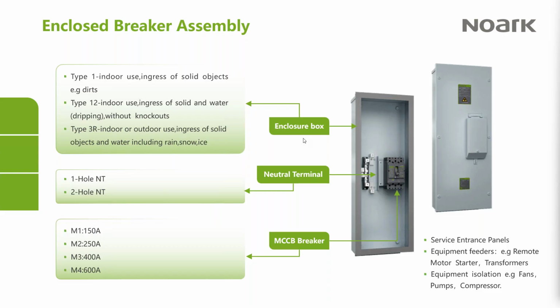I just want to show the enclosed breaker assembly, what it looks like inside. We talked about earlier, we do offer a type 1, type 12, and type 3R enclosure with the options of either a 1-hole or 2-hole neutral. We also provide options for 4 breakers, ranging from 150 amp to 600 amp. If you look to the enclosure to the right, we prefabricate the enclosure at the factory. To help with lead time, they prefabricate it and then send it to the assembly areas. All we have to do in assembly is put in the breaker and the neutral, and it's ready to go.